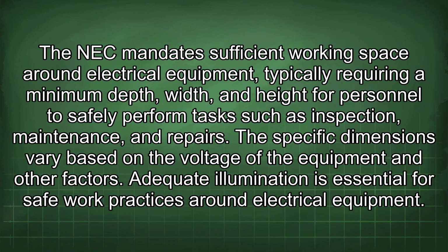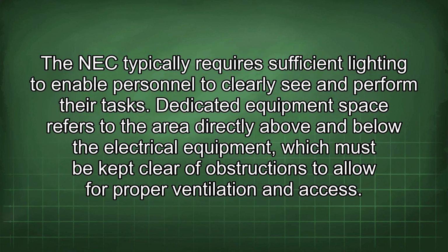The NEC mandates sufficient working space around the electrical equipment, typically requiring a minimum depth, width, and height for personnel to safely perform tasks such as inspection, maintenance, and repairs. The specific dimensions vary based on the voltage of the equipment and other factors. Adequate illumination is essential for safe work practices around electrical equipment. The NEC typically requires sufficient lighting to enable personnel to clearly see and perform their tasks.